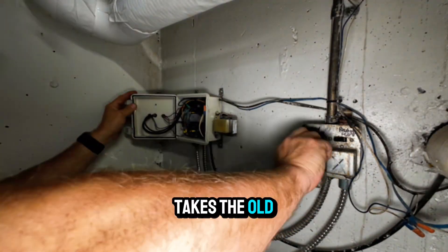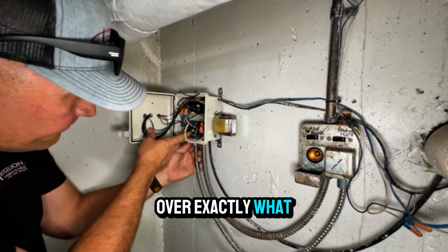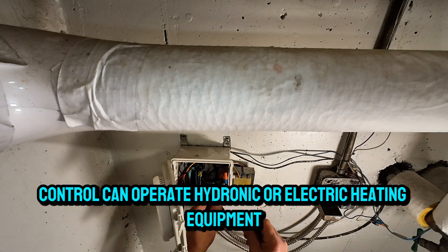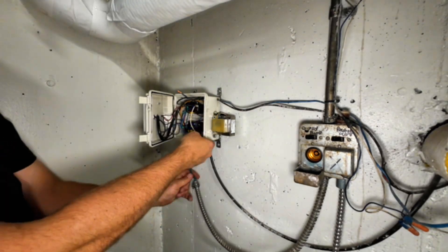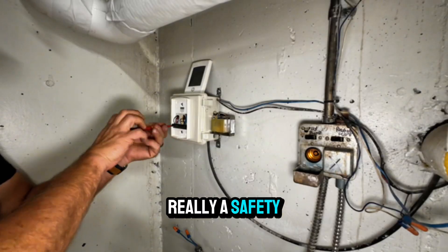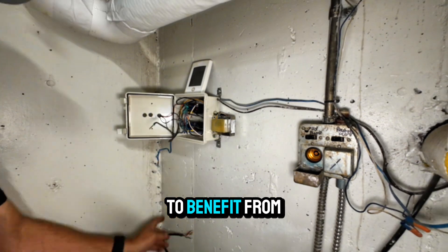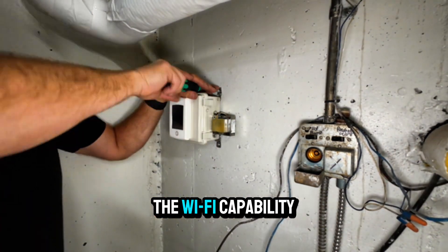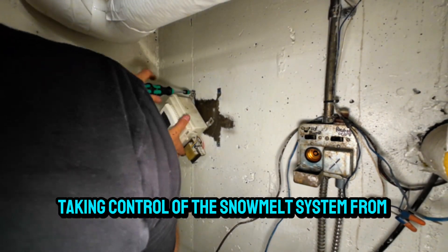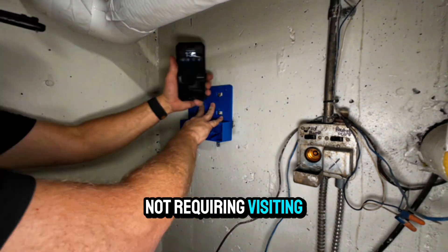As Andy takes the old control off the wall, removing power and disconnecting the wires, I'm going to go over exactly what a Wi-Fi snowmelting control is. From Tekmar, this 670 control can operate hydronic or electric heating equipment. It's designed to melt snow and ice from roads and walkways, so this is really a safety device. This condo project is really going to benefit from the Wi-Fi capability because they've got a building management company taking control of the snowmelt system from a remote location, not requiring visiting the site.